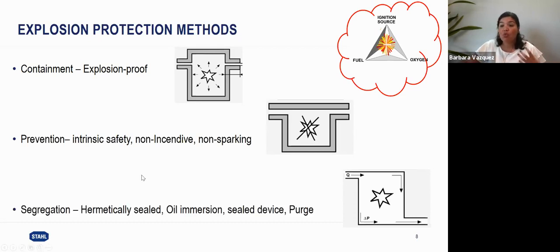And the last principle will be segregation. So with segregation, we're saying we're going to isolate our electronics from our explosive atmosphere. So when the spark, the heat happens, it cannot react with the explosive atmosphere because they are isolated, right? Examples of these will be purge and pressurization, right? You have air, instrument air. So spark comes, and that's it. Oil immersion, encapsulation, hermetically sealed. Those are some examples.